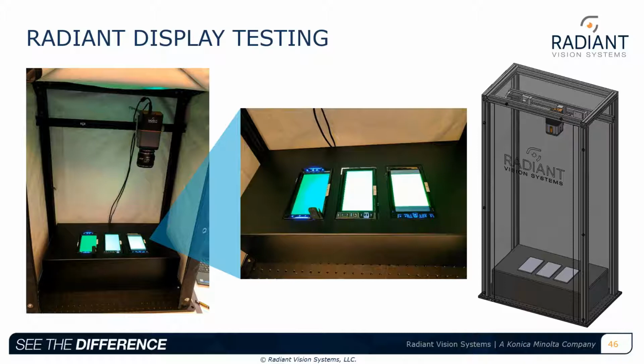We looked at defining working distance, and what we found was there is variation if you change your working distance from the DUT to the camera itself, which is the reason we've locked down the measurement methodology of using a 0.5 meter working distance. But the next couple slides will show you a comparison from a system repeatability standpoint of using 3 different cameras and what that variation looks like.